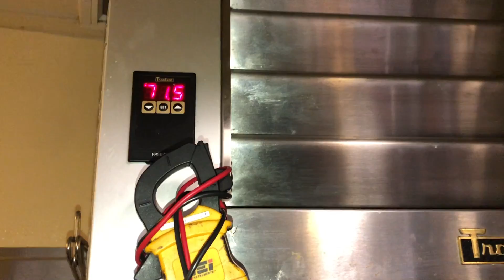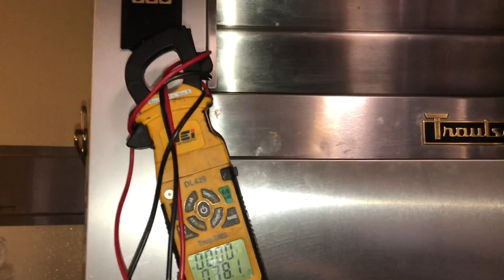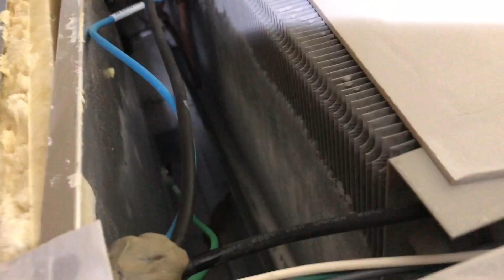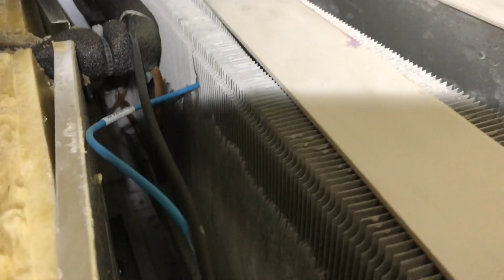So I need to get into here and check my ohms value on my cabinet sensor. I might have a bad cabinet sensor. It might have caused this evaporator coil to ice up. It goes into defrost, but the computer sees the temperature of the cabinet too high, brings it out of defrost. It's a possibility. Flip this thing around and look, see, that coil was iced up yesterday. That side of the coil had de-iced, sitting overnight, and this side hadn't, so I got to de-ice that. But the cabinet sensor is not reading correctly down there. Possibly. I'm going to check the ohms value.